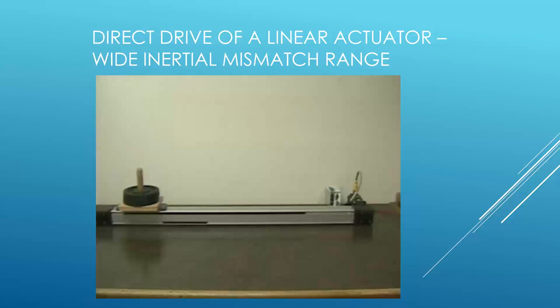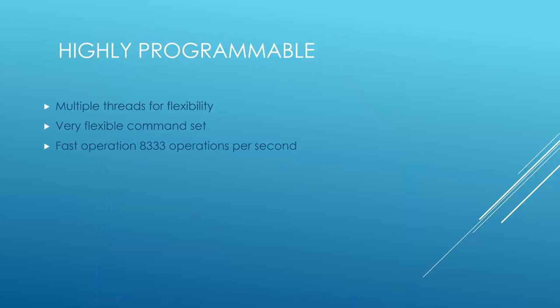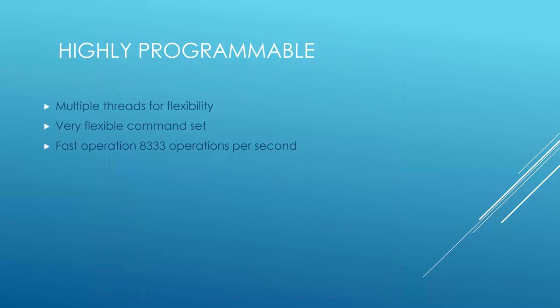You'll lose stability in the system if you have the gains high. If you don't have the gains high, you have poor control at the lower frequency range. So in order to have good control, you'd like to have a wide bandwidth with good gain. And with a wide ratio of inertias, you end up having a very wide range of gains versus frequency, that if you don't have ways to stabilize, you just can't have the tightness of control with the high inertia out there.